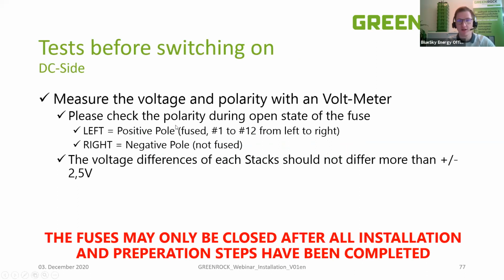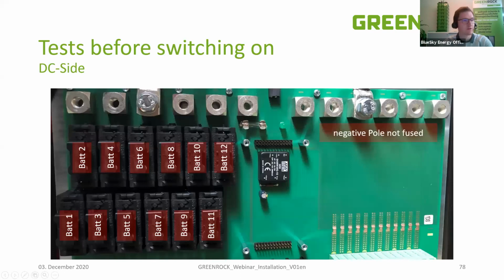Before starting up a system, always check all the wires and check all the voltages. You can also check each stack voltage, which is recommended. On the minus pole, all these connectors and plugs are connected to the other. Using the second pole of your voltmeter, you can measure the battery voltage, and you have to ensure the battery voltages do not differ by more than 2.5 volts. Use the negative part of your voltmeter, and on the bottom of the fuse holder of each connection point, use the second wire so you see the correct battery voltage.